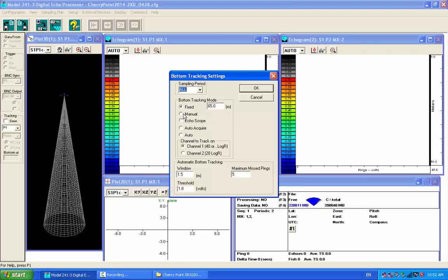auto acquire: if it loses bottom, it will search the whole water column on the next ping and look for the next echo at range that has a voltage greater than whatever you set here. It has to exceed that voltage. One way to look at that when you're setting up auto bottom tracking parameters is to bring up the echo scope and look at what your bottom voltage is. Oh, it's bouncing between 2 and 10 volts, so it doesn't look like it goes much below 2. Let's set it at about 1.5 volts. That should meet that criteria.